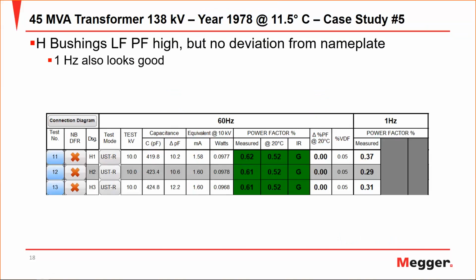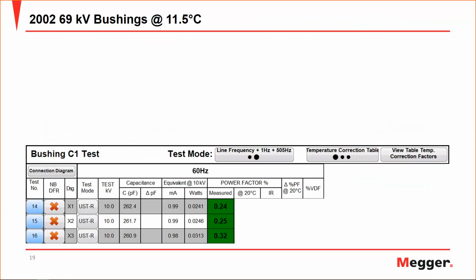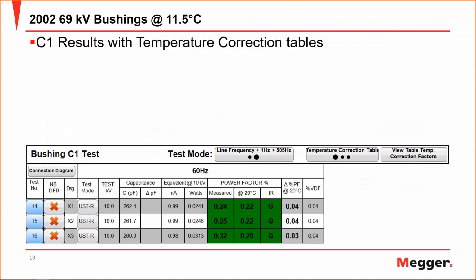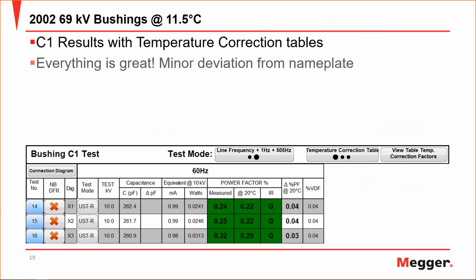So on this same transformer, this customer performed the line frequency and 1 Hertz testing on the high side and also on the low side bushings. If we look at the low side bushings, corrected with table correction factors, everything looks great. There's only very minor deviations from nameplate. So without any additional information, a customer such as yourself or the one in this study would say, all of these bushings are in excellent condition. We can put them back into service without any expected problems to come from them.